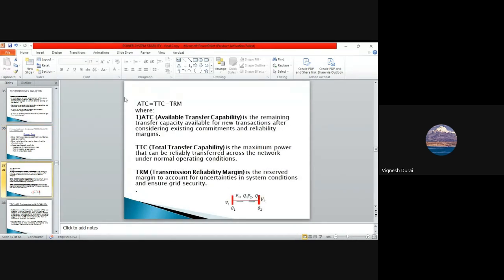Okay. ATC, or available transfer capacity, is the remaining transfer capacity available for a new transaction after considering existing commitments and reliability margins. This ATC is equal to TTC minus TRM. TTC means, suppose there is a transmission line, the total transfer capacity is the maximum power that can be reliably transferred across the network under normal operating conditions for a transfer from a bus to a bus. Okay. This ATC is the available transfer capacity. If you take total capacity minus reliability margin, you will get this available transfer capacity.